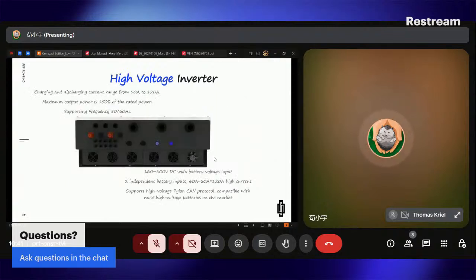So this is the bottom of the high voltage inverter. We can see the charging and discharging current ranges from 90 amps to 120 amps. It depends on the power and exact model. And the maximum output power is 150% of the rated power, which means when you have some inductive load, it will be easier for the inverter to handle it. And the frequency is 50 and 60 hertz. It's the same as the low voltage. Different is that we have 2 independent battery inputs. We can see the battery terminals here. Actually, we can even connect one group of high voltage batteries to 2 ports so that we can support 120 amps high current. And we also support the Pylon CAN protocol, which means it's compatible with most high voltage batteries on the market.